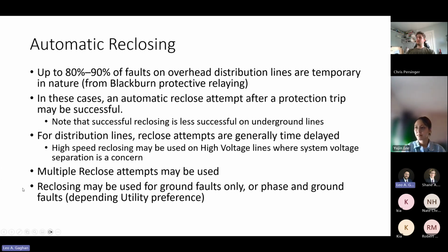And then sometimes people want to use reclosing just for ground faults. They might do that, right? Because even statistically, within that 80-90%, it's an even much higher percentage that you're going to successfully reclose for ground faults. Phase faults, maybe less, but that's usually a utility preference. Some like to reclose for all, some just ground. You've got to work with them and get a feel for what they want.